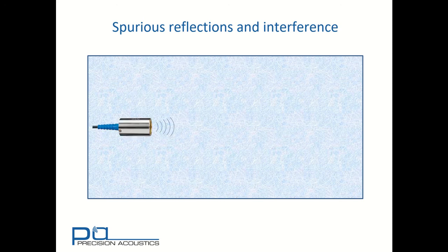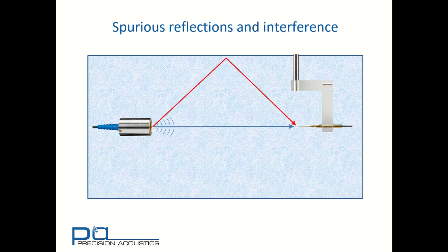There may also be a problem if we're using a transducer with a broad radiation pattern. Consider here a transducer radiating into water. The direct path between the transducer and the receiving hydrophone is shown in blue. But if the transducer has a broad radiation pattern, there may also be an indirect path, here shown in red, that arises from reflections at either the water-air surface or at the tank edges.